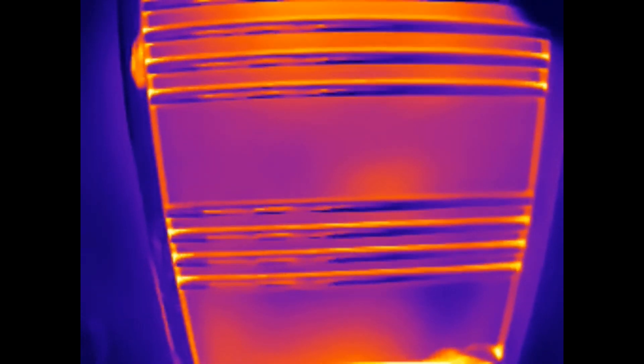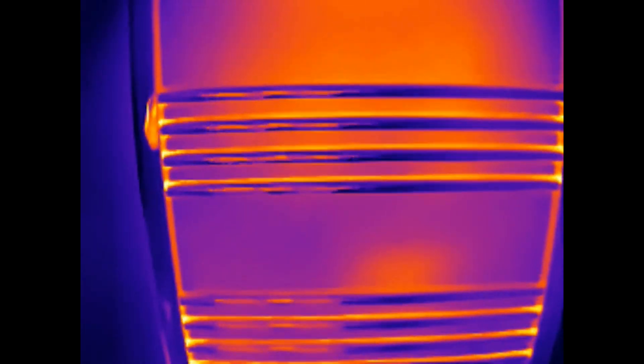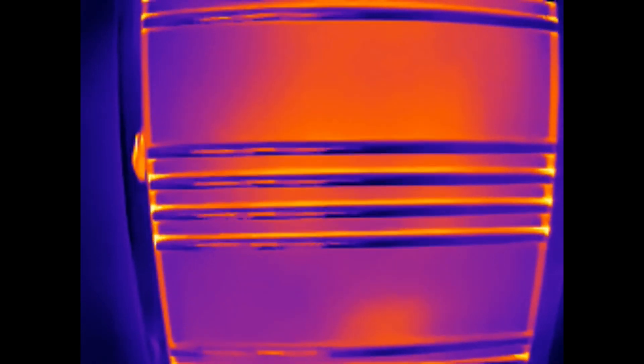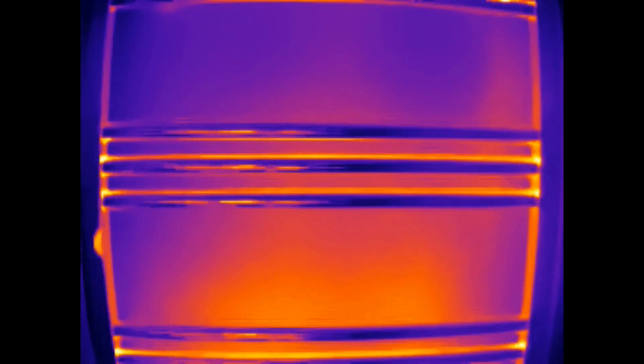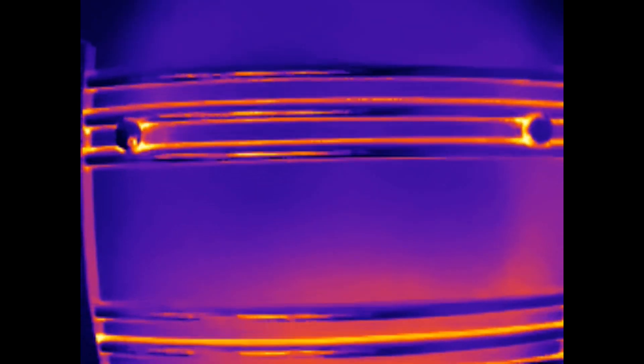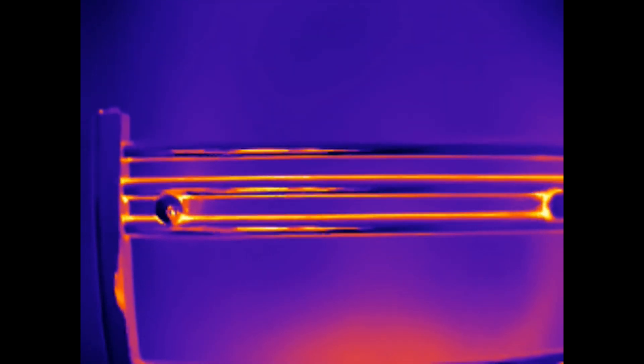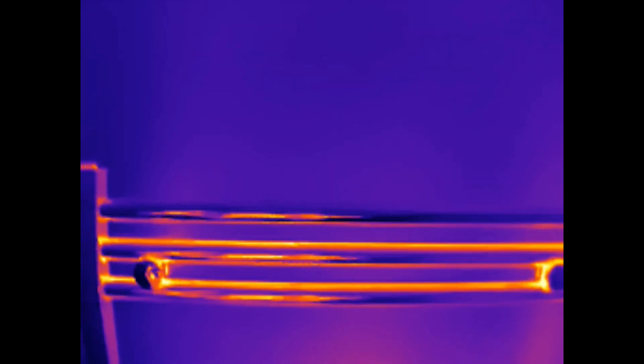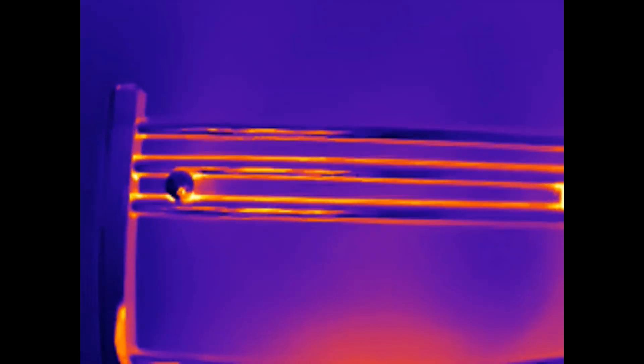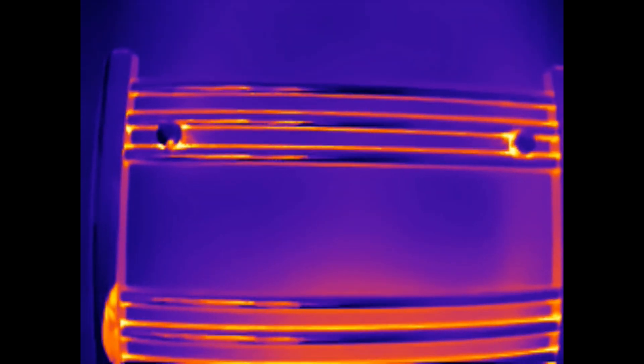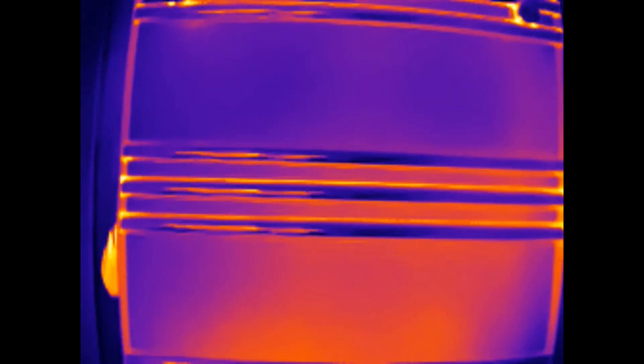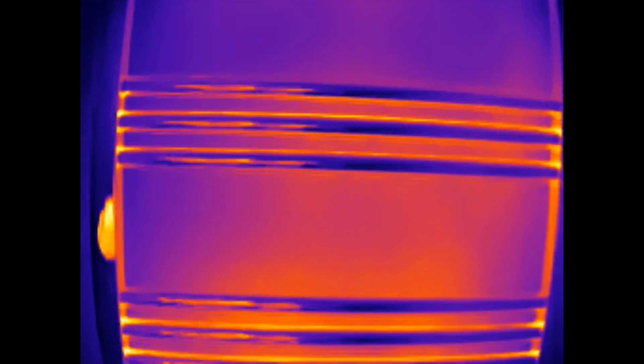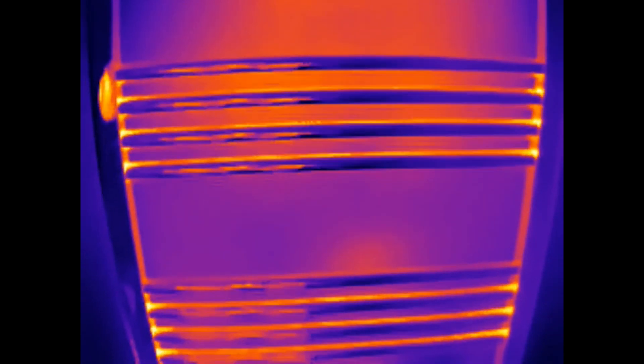Looking at one in the bathroom, this is where the emissiveness of the material comes into play. We're not getting a very good reading on the chrome plated radiator here, but if we look at the effect of the radiator on the wall behind, you can see it's been heating up the wall on these lower areas. On this top section of radiator, the background wall isn't quite so hot, so perhaps I may have a bit of an air pocket in that region. Holding on to it, it does feel slightly colder than the rest of the radiator when it should be the hottest point being at the top.